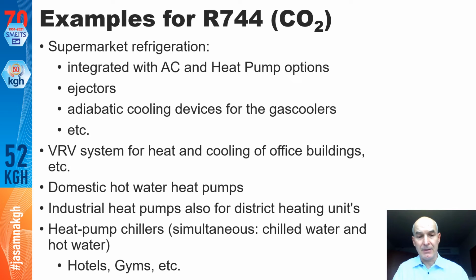Mainly with CO2, and some do have hydrocarbon systems, but none of them is continuing with F-gases. Heat pump chillers, as I showed you, are very attractive, especially if you have a higher temperature difference on the chilled water side, the process plant. You can utilize a very interesting two-stage ejector solution, which is very energy efficient, very promising.